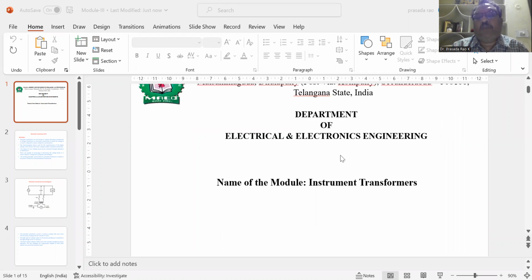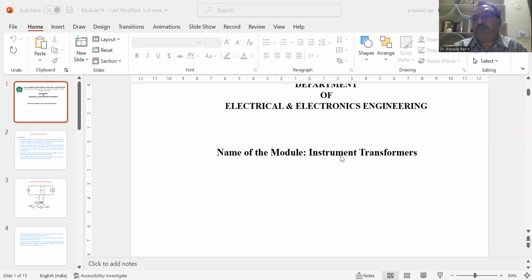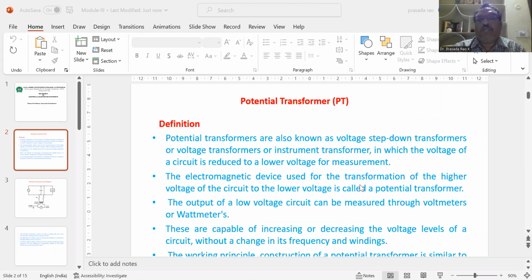Today I am going to explain about instrument transformers. The instrument transformers are basically meant for measuring high voltages and currents. They are classified into two types: the potential transformers and the current transformers. The potential transformers are also known as voltage step-down transformers, or simply voltage transformers or instrument transformers. In a potential transformer, the voltage of a circuit is reduced to a lower voltage for measurement.